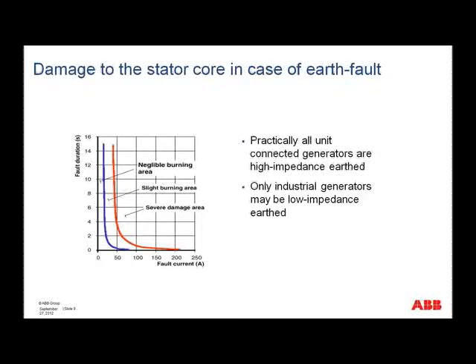Now this picture shows the withstand capability of the stator core to ground fault currents. And if we study the curves here, we will see that it shows an area where there will be negligible burning, an area where there will be slight burning, and an area where severe damage can occur. Now, as you can see from this, the stator core can withstand very small ground currents, even for short duration.